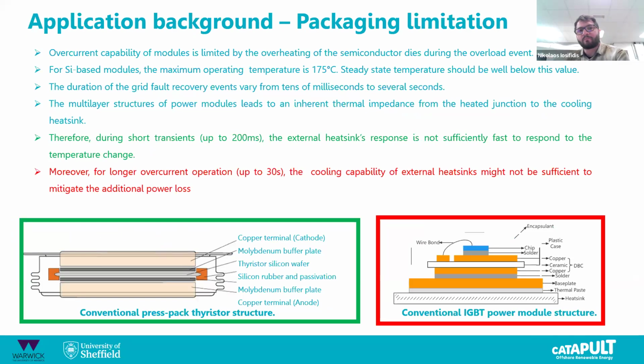Next one, please. The overcurrent capability is limited by the overheating of the semiconductor chips, be it in a thyristor, which is a disk, or in IGBTs and diodes, or maybe later in silicon carbide MOSFETs. For silicon-based modules, the maximum operating temperature of silicon is 175, and the steady state should be much lower than that. Grid fault events can last from tens to hundreds of milliseconds all the way to, let's say, 30 seconds. And the multi-layer structures of power modules, the conventional press pack thyristor module and the IGBT power module, have so many layers, 7 for the IGBT, with materials of different thicknesses and different thermal conductivities.